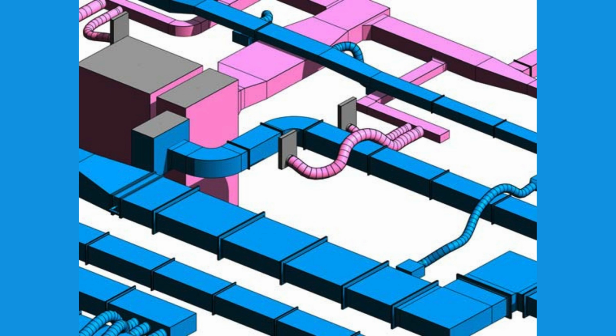3. Minimize pressure losses. Friction and turbulence within the ductwork reduce air pressure. To minimize pressure losses, the following practices are recommended. Sizing ducts appropriately. Avoid undersized ducts that increase air velocity and friction losses. Oversized ducts, while decreasing velocity, can also be inefficient due to increased surface area for heat transfer.